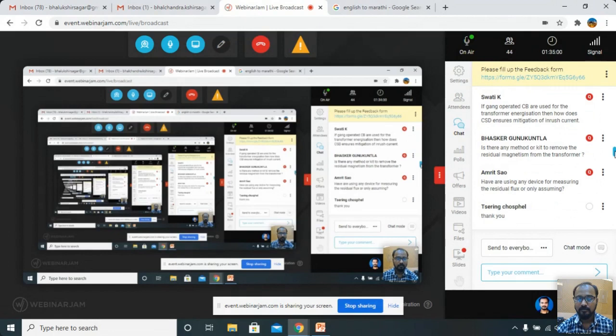Let me just tell you which is the next webinar that we are going to conduct. We are going to conduct the next webinar on third harmonic leakage current measurement, compensation and analysis. You will probably be aware that we use third harmonic resistive leakage current measurement, also called LCM, leakage current meter, for monitoring the leakage current of surge arresters in order to assess the healthiness of the surge arresters. This next webinar is going to be on 31st of October, that is 2 weeks from today. I request you all to join us to get insights on this assessment of the health of the surge arresters.